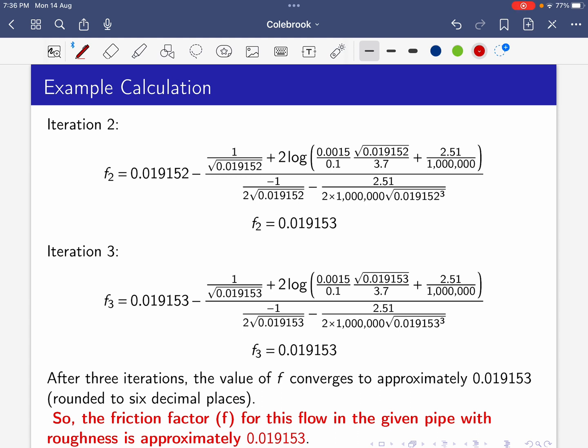After three iterations, the value of f converges to approximately 0.019153 rounded to six decimal places. The friction factor for this flow in the given pipe with roughness is approximately 0.019153. After getting the friction factor, we can easily calculate pressure drop, major loss, or whatever is needed. Now we understand how to calculate friction factor from Colebrook equation.